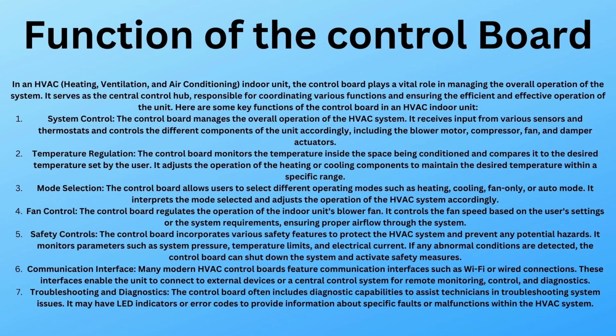The one thing is system control. The control board manages the overall operation of the HVAC system. It receives input from various sensors and thermostats and controls different components of the unit, including the blower wheel, compressor, fan, and damper actuators. What they mean by damper actuators: if you have a 2-story home and a 5-ton system that fundamentally can't cool the upstairs efficiently, maintaining say 80 degrees, you can put control dampers in.